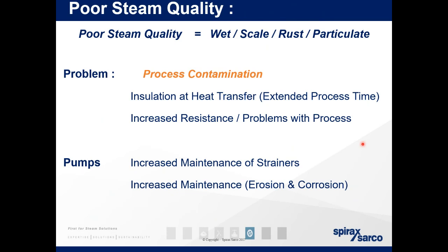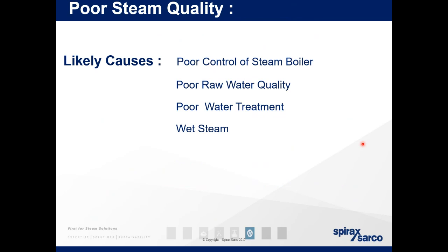Then the resistance, the extra insulation that's there, is going to cause an issue on you reaching process temperature. So the problem you have with pumps is increased maintenance of strainers, increased maintenance, erosion and corrosion. So all of this from the carryover or from pumping the media around. Likely causes, so poor control of steam boiler. So if you're getting a lot of carryover, if you're flattening the boiler, so effectively decreasing the volume of steam in the boiler, it's going to give you issues with chemical carryover, loss of steam, loss of temperature.